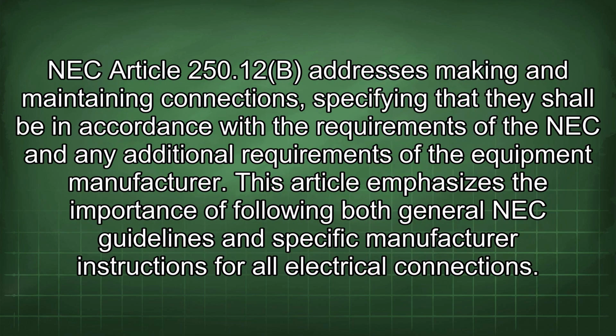This is a fundamental requirement ensuring that equipment is installed as the manufacturer intended. NEC Article 250.12(B) addresses making and maintaining connections, specifying that they shall be in accordance with the requirements of the NEC and any additional requirements of the equipment manufacturer. This article emphasizes the importance of following both general NEC guidelines and specific manufacturer instructions for all electrical connections.